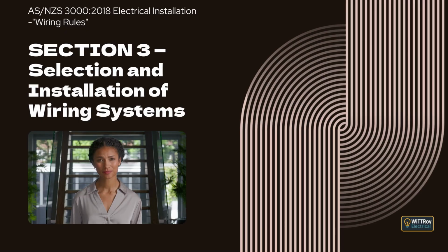This clause explains that crimped or compressed connections must be securely retained within a suitable crimping device and made using tools and techniques specified by the manufacturer. Clause 3.7.2.4, Mechanical connection devices. This clause states that mechanical connection devices may be used where they comply with the relevant standard, do not rely on compression of insulation for electrical contact, have suitable short-circuit ratings, provide long-term current carrying capacity not less than the connected conductors, do not deteriorate if reused where permitted, include manufacturer information for correct use, and are installed using approved techniques.